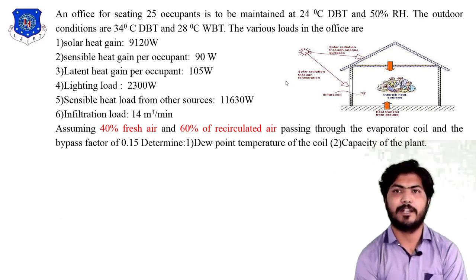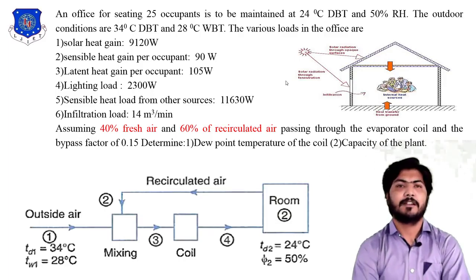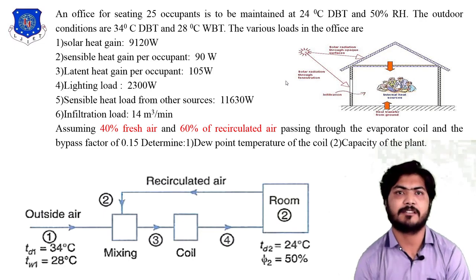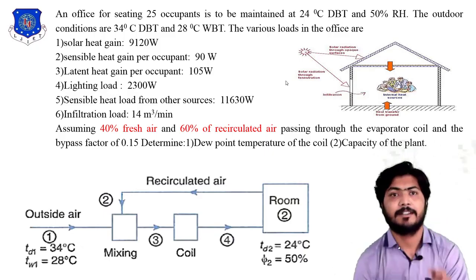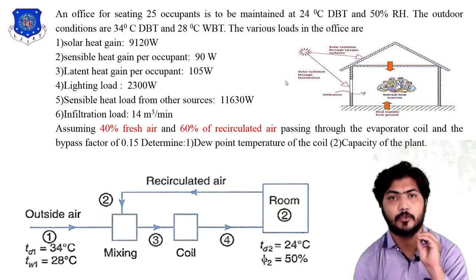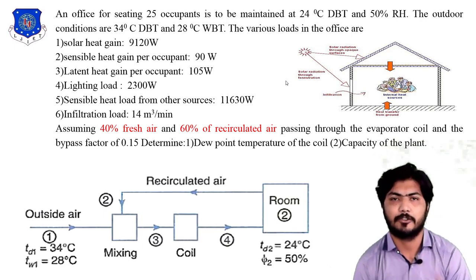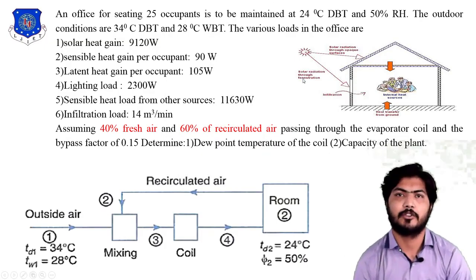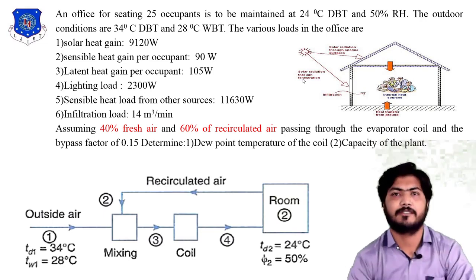We are to determine the dew point temperature of the coil and the capacity of the AC plant. This is explained using a diagram: outside air at condition point 1 comes into the mixing chamber where 60% recirculated air and 40% fresh air are mixed. This mixing air passes through the cooling coil, since the required temperature is lower than the outside air. After the cooling coil, cold air is supplied to the room, heat is absorbed from the room, and the air is again recirculated to the mixing chamber — this is the whole cycle.